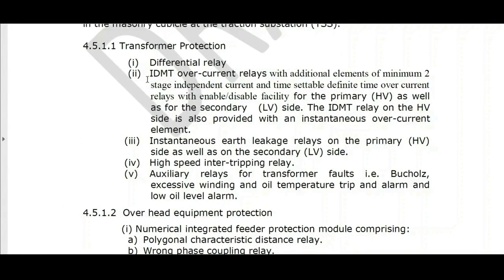For this, several curves are there. We normally coordinate. This is called relay coordination. That is, if you have 2 relays, if relay 1 fails to trip, then relay 2 will trip. That means relay 1 should have, let us say, 1 second delay, and relay 2 should have something more than that, 1.5 seconds. Then only I allow relay 1 to trip first. So allowing the previous relay to trip is called relay coordination. IDMT is one of the tools to do it.